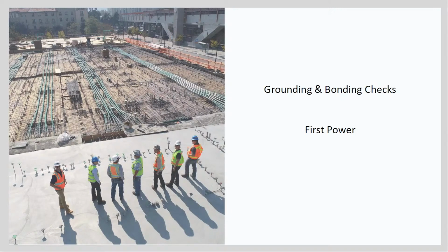So following that, then first power can be applied to control and protection cubicles, communication cubicles, any of the racks that are controlling any of the equipment on site. Once all the cables have been pulled and terminated, then the cubicles can be energized for the first time. Some basic checks as you're going through this would be obvious power polarity checks. You want to confirm that the cables are installed correctly, that you're not going to provide power backwards to a cubicle and cause damage to the equipment or cause any safety hazards.